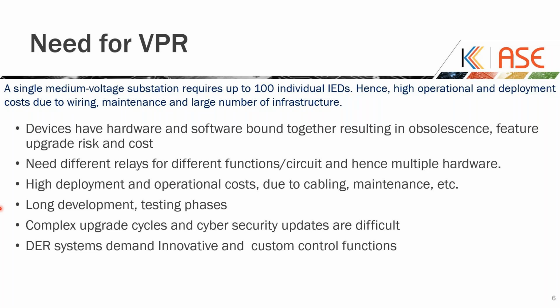A utility often needs to procure different relays for protection schemes, requiring maintaining and training in multiple vendor-dependent hardware and software tools. The cost involved in relay commissioning, operation, and cabling adds more to total operation cost. It takes more time to test and develop both the hardware and the software.